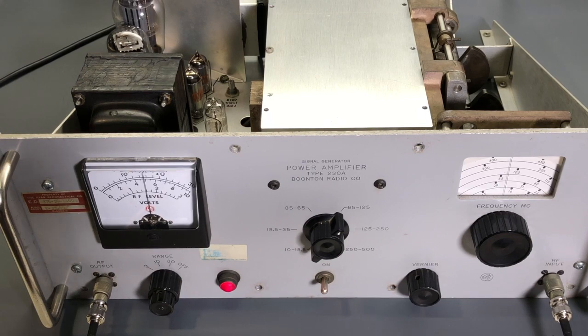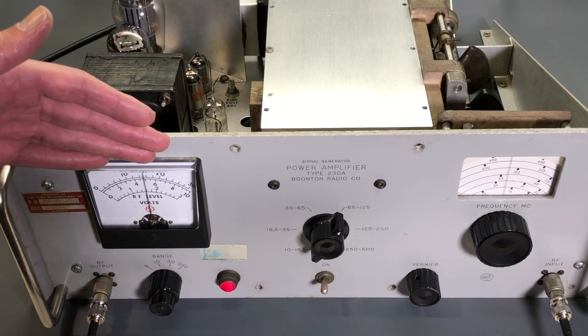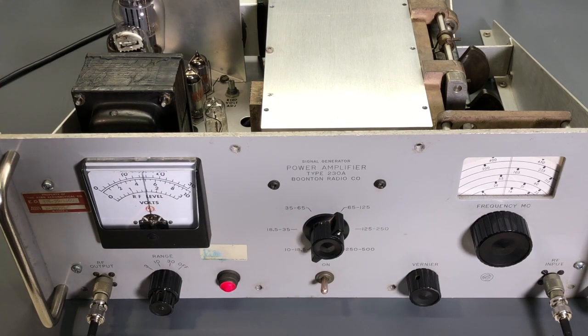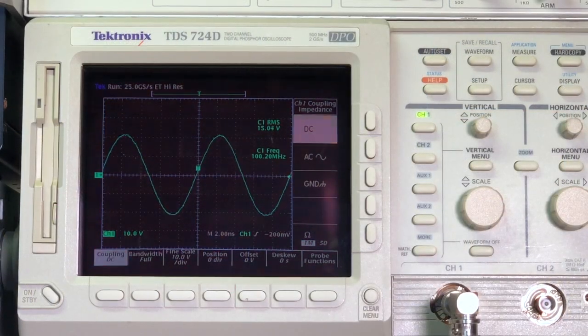Okay, I now have the RF signal generator set to 315 millivolts output, still at 100 megahertz. And you can see on the RF level meter right here, it's indicating 15 volts. The oscilloscope is also showing 15 volts. So 15 volts into the 50 ohm dummy load gives us 4.5 watts of power. So this amplifier is rated 4.5 watts, and it's able to meet that specification. So it's looking very good at this point. Okay, here's a view of the oscilloscope, and you can see the 15 volt signal at 100 megahertz. So 15 volts into the 50 ohm dummy load is giving us the 4.5 watts of power coming from the amplifier.